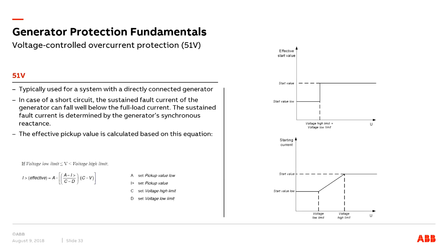So the next protection consideration is voltage controlled overcurrent protection. And why voltage controlled overcurrent protection? Because in the event of a fault, the terminal voltage drops or changes. This is typically used for a system with a direct connected generator. In the case of a short circuit, the sustained fault current of the generator can fall well below the full load current. Okay, so a regular overcurrent may not operate in this situation. The sustained fault current is determined by the generator's synchronous reactance, as we discussed earlier, and the effective pickup value is calculated based on the equation here.